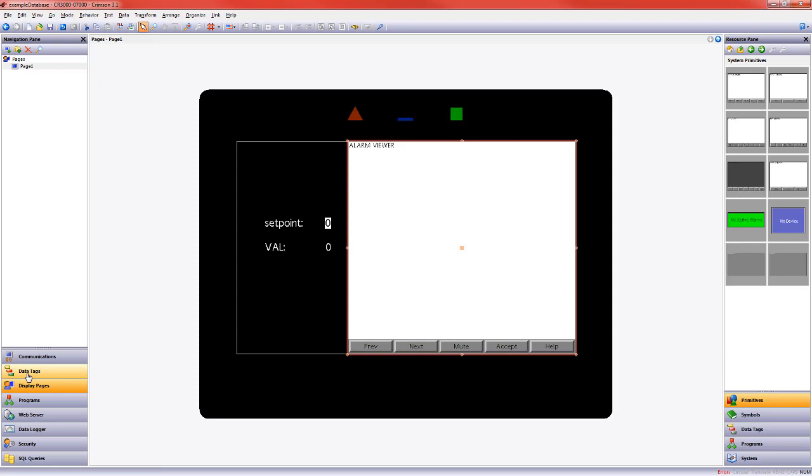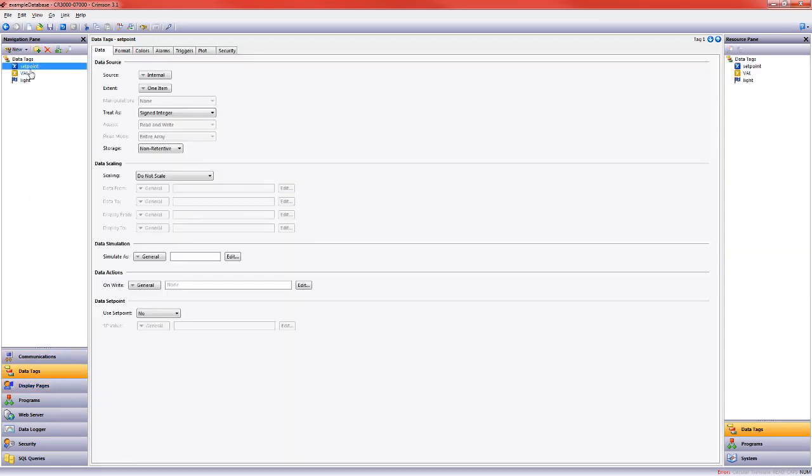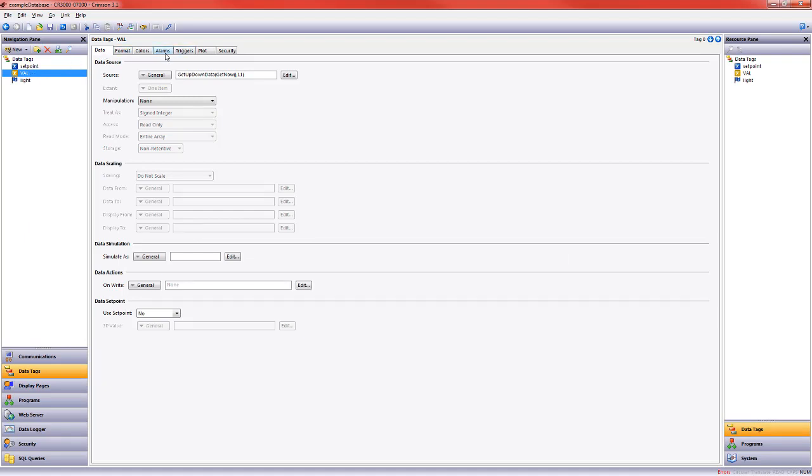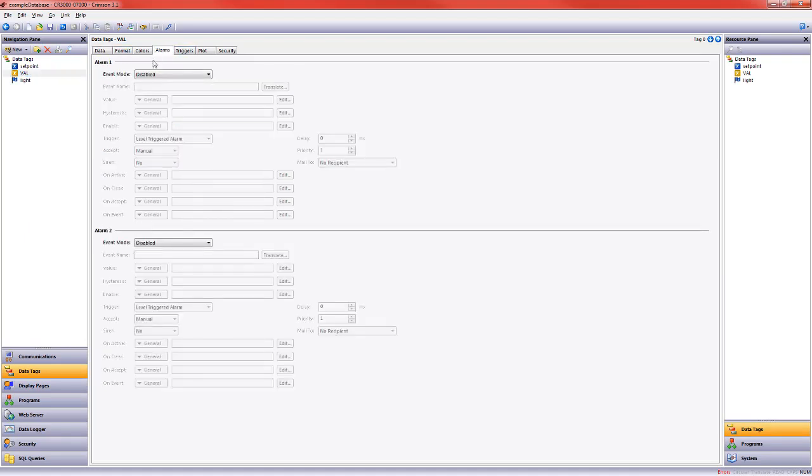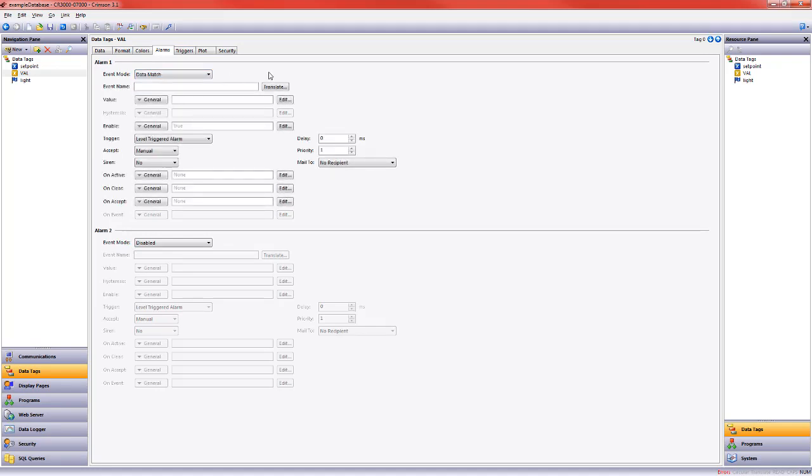Now let's set up an alarm on our value data tag. I'm going to come here, and in the editing pane, I'm going to come across to alarms, and I will choose data match. What data do we want to match? In our case, we want to match the setpoint. I come to resource pane, click and drag. The value we're comparing against is setpoint. When we send this to our database, it will be at zero because we haven't given it an initial value. We aren't assigning it a value through a Modbus register or through a program.